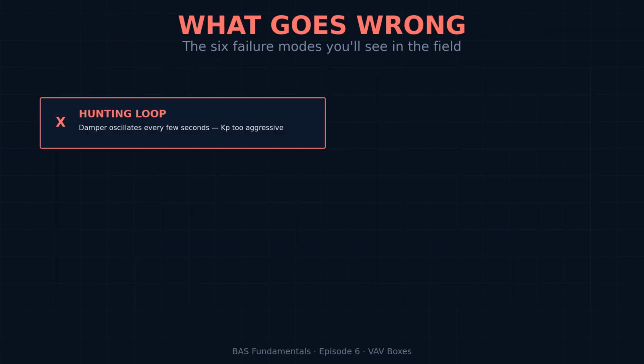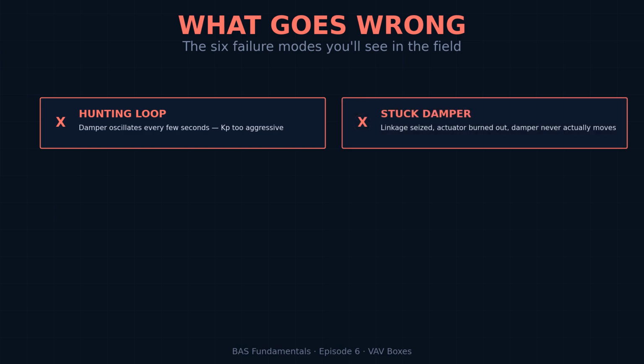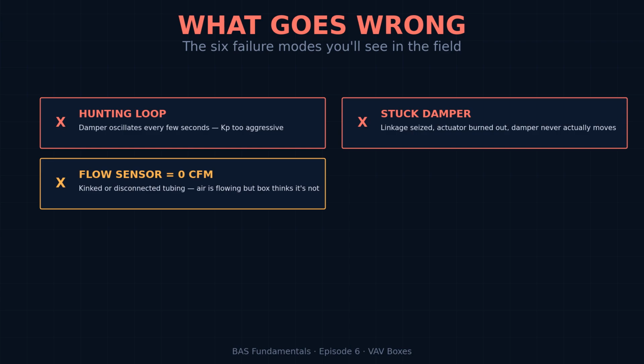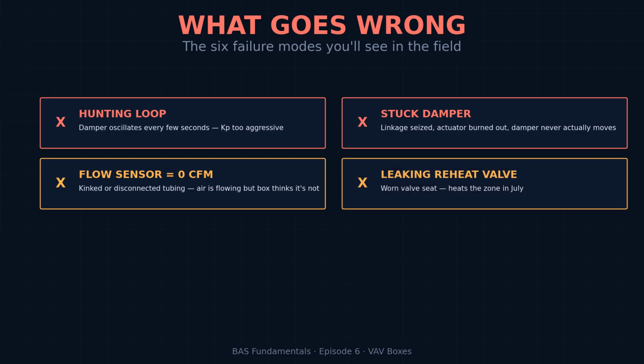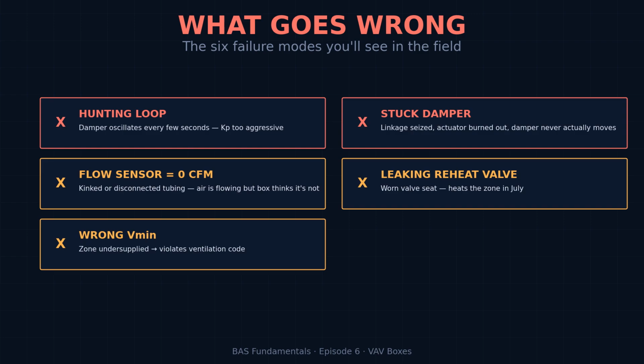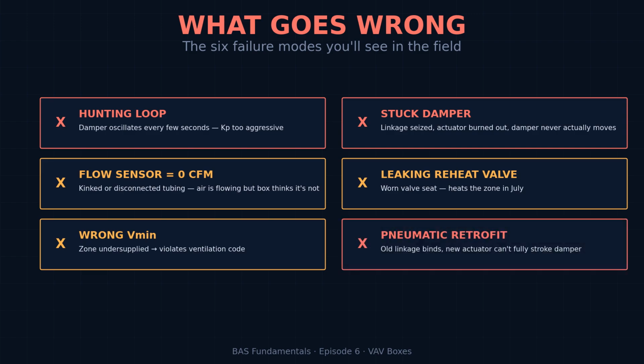What actually goes wrong in the field? Hunting loops, where the damper oscillates open and closed every few seconds because the proportional gain is too aggressive. Stuck dampers, linkage seized, actuator burned out, damper never actually moves. Failed flow sensor reading 0 CFM even though air is clearly flowing, usually kinked or disconnected tubing. Reheat valve leaking by, heating the zone in the middle of summer because the valve seat is worn. Wrong Vmin set for the zone, violating ventilation code. And classic pneumatic to DDC retrofits, where the mechanical linkage is still binding on an old damper shaft and the new actuator can't fully stroke it.